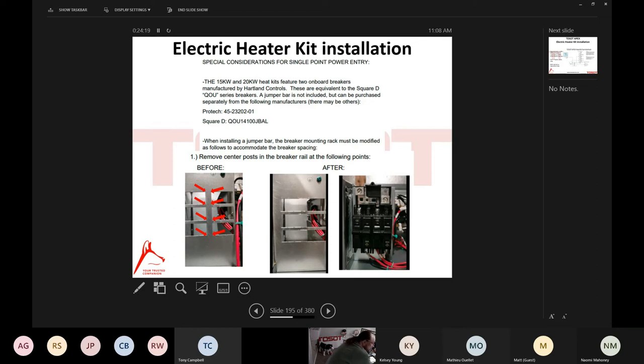They told me, and I don't know if this is unique to Quebec, maybe you guys can enlighten me here again. They were saying that this single point jumper bar by Canadian code has to be provided by the breaker manufacturer, not by ProTech, not by Square D. Now, maybe Square D and ProTech make breakers. I don't know if they made this one, but apparently that was an issue brought up by those guys, and they have the answer to it. So if that's a problem for you, I would suggest talking to Daniel or Yves or David out of Deluxe Air in Quebec, because they have the answer if that's a unique problem for you guys as well.